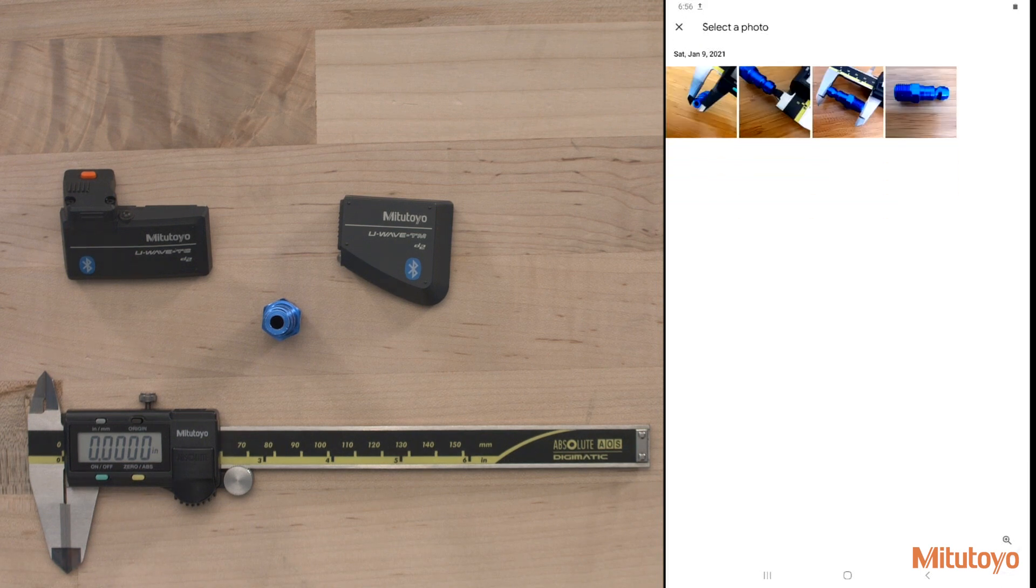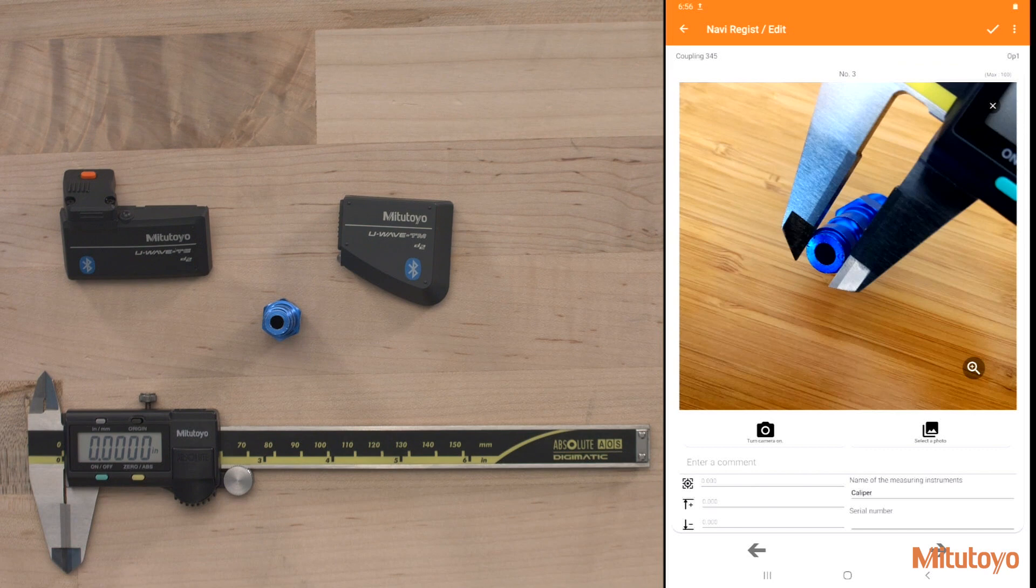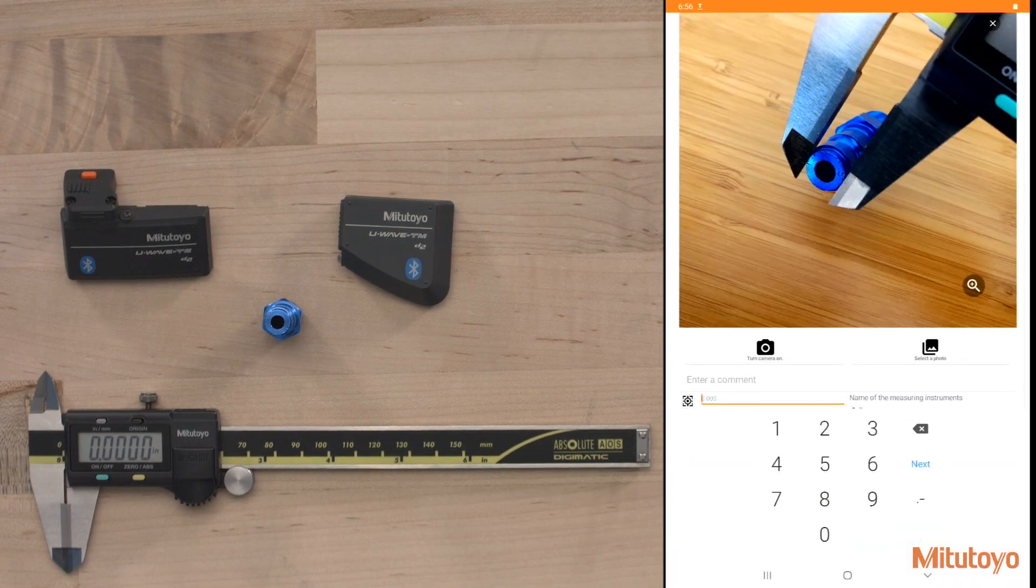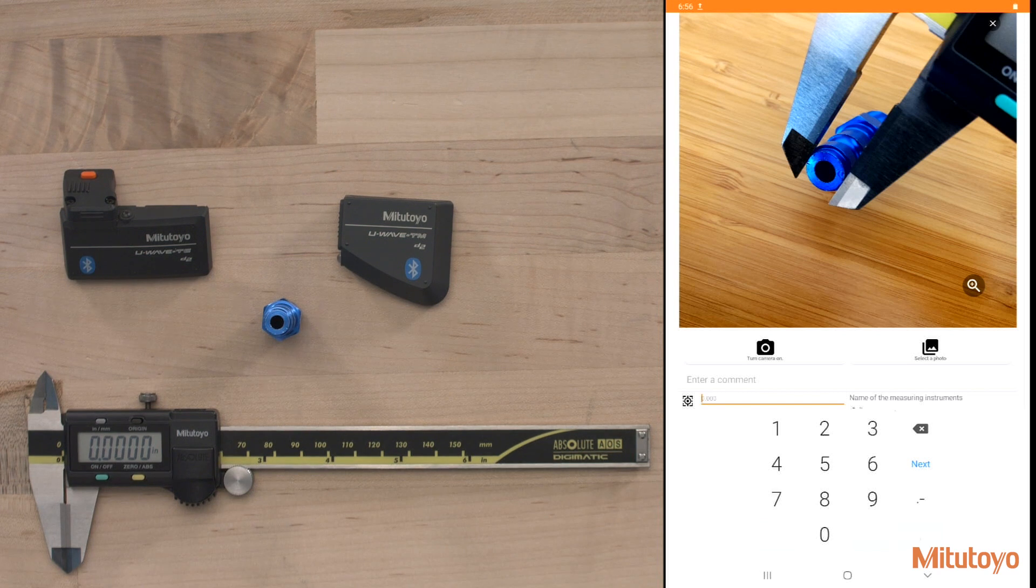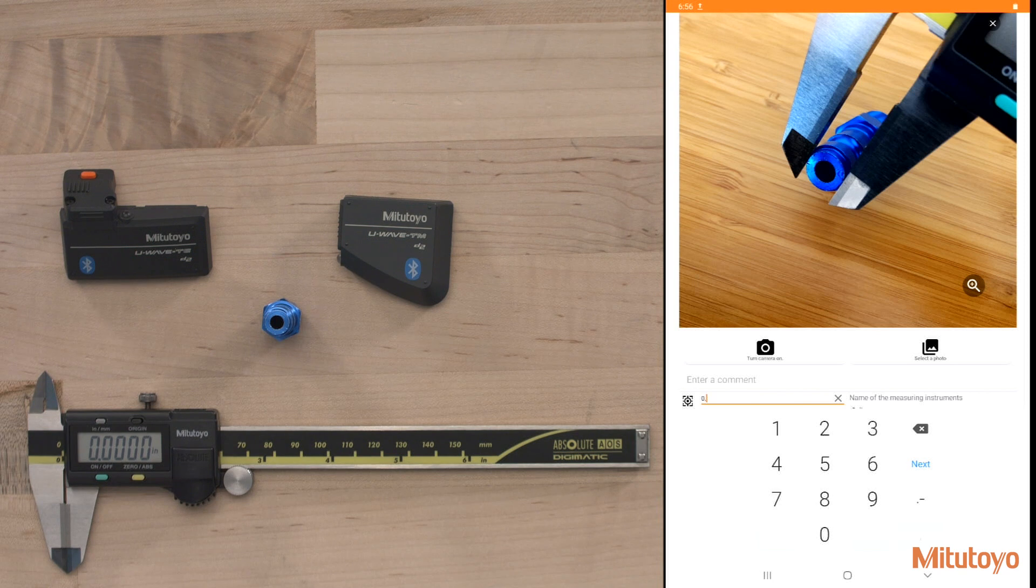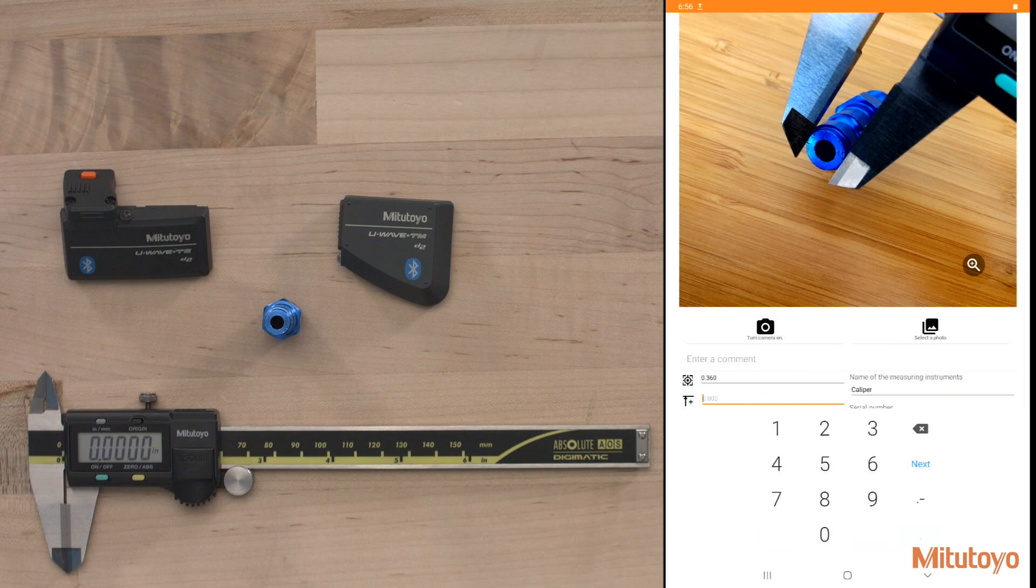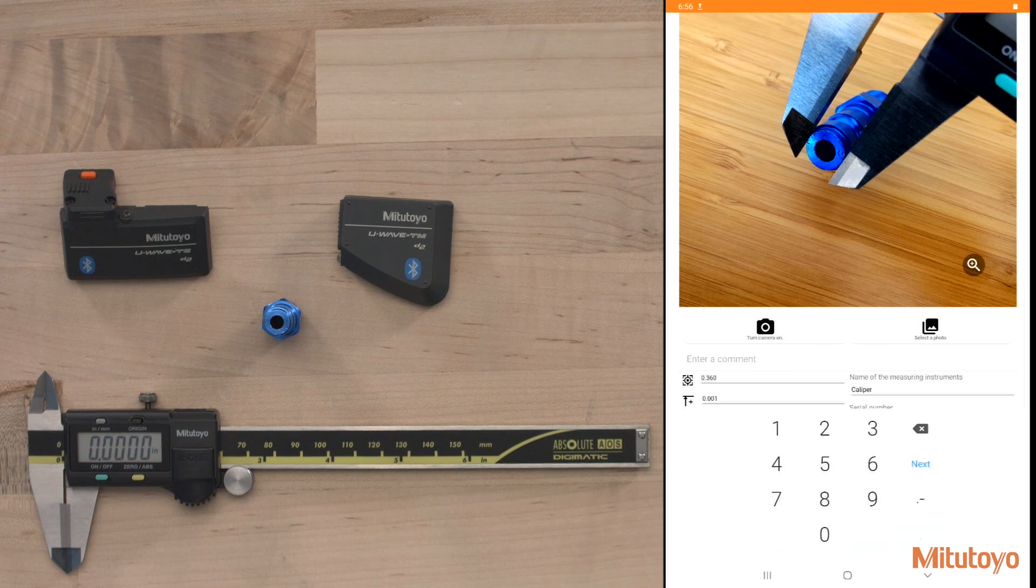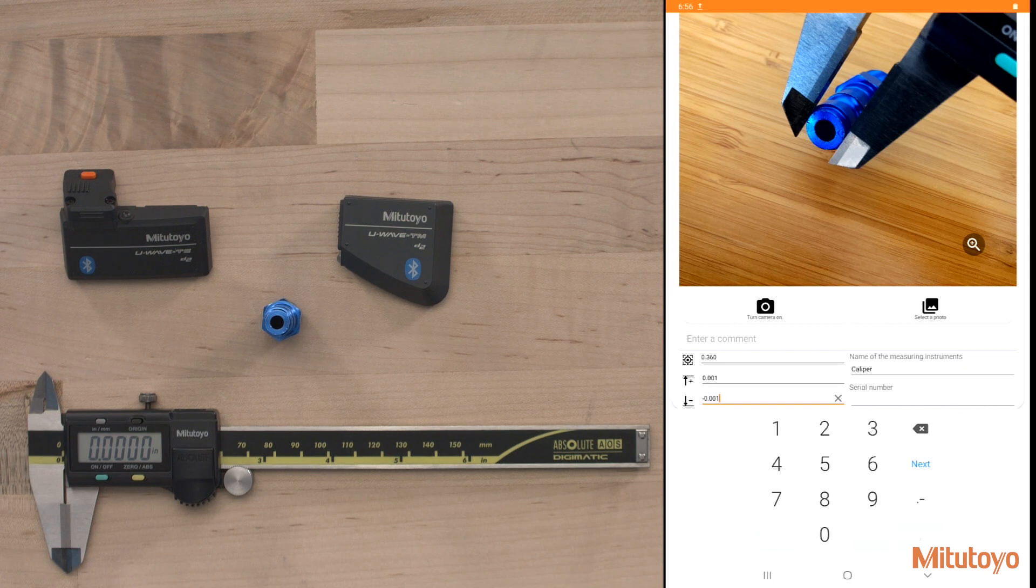And lastly, let's go ahead and do the outside diameter. These pictures are going to be really helpful for operators who are unfamiliar with the parts. This part has a lot of different outside diameter. So it's nice to know which one it is to avoid taking incorrect measurements. This one nominal is going to be 0.360. And let's tighten up this tolerance here just a little bit. 0.001. And this one will be minus 0.001.